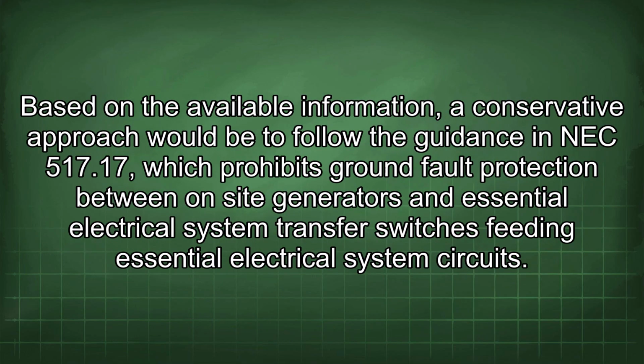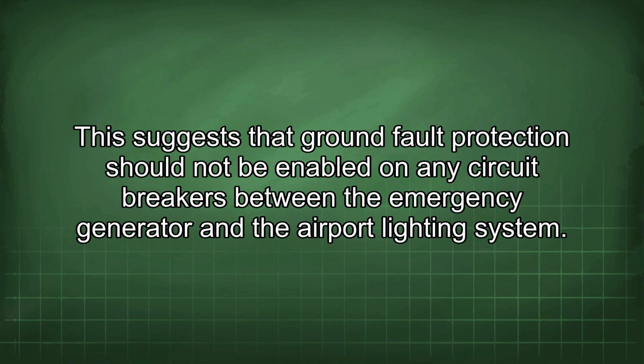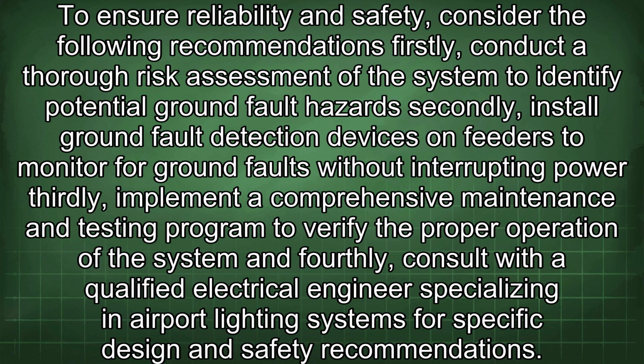Based on the available information, a conservative approach would be to follow the guidance in NEC 517.17, which prohibits ground fault protection between on-site generators and essential electrical system transfer switches feeding essential electrical system circuits. This suggests that ground fault protection should not be enabled on any circuit breakers between the emergency generator and the airport lighting system. To ensure reliability and safety, consider the following recommendations.